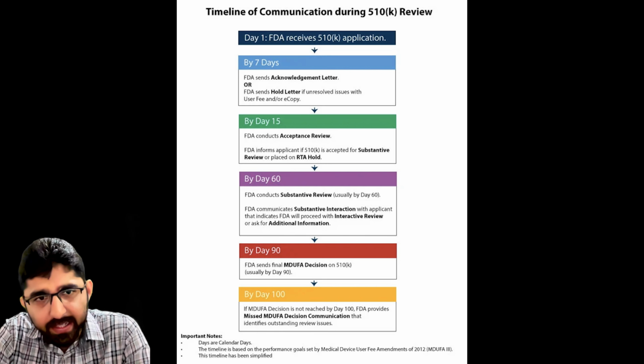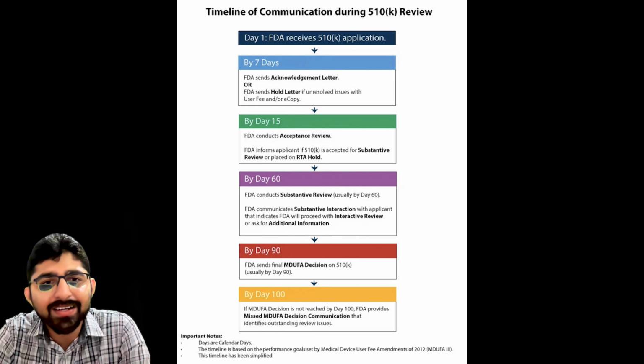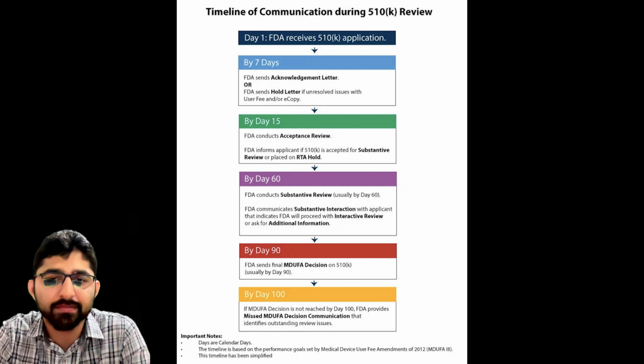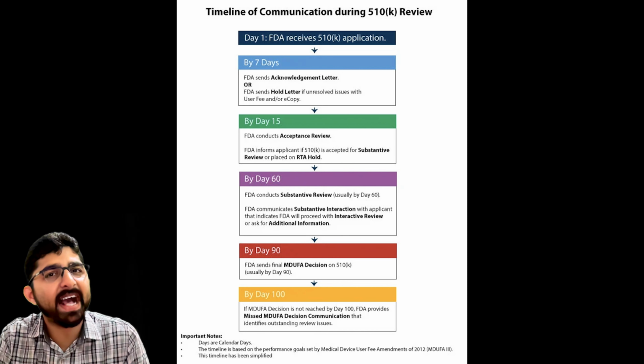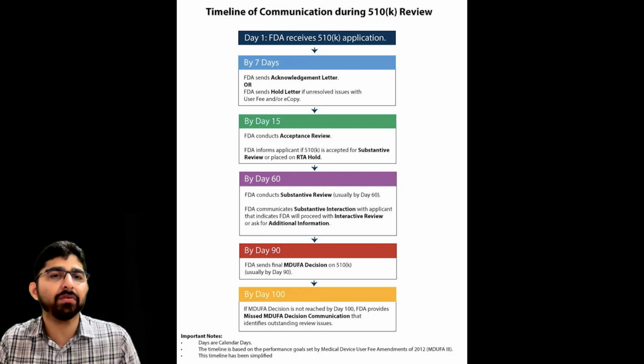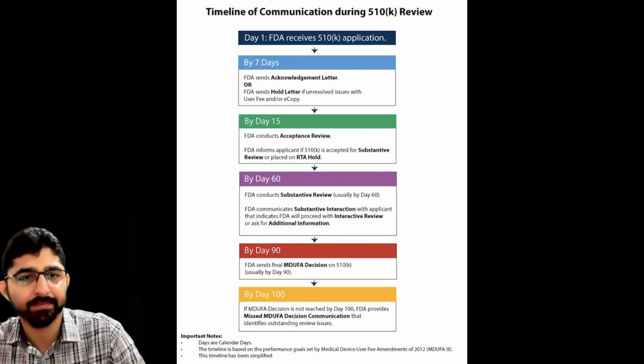By day 15, FDA will conduct the acceptance review. FDA will inform the applicant that the 510(k) is accepted for substantive review or placed on RTA hold.